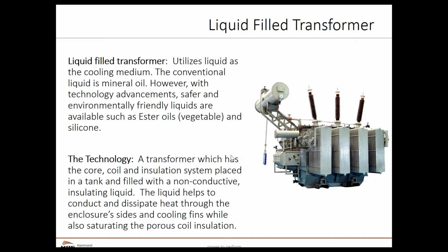In the case here, the picture we're showing is really what we term a high voltage transformer versus a medium voltage transformer. And high voltage transformers, as we will talk about soon, really are the domain of liquid filled. Medium voltage or dry type transformers really are only applicable to applications that are 44 kV and below. Anything higher than that, and you're really probably looking at liquid filled. There are some transformer manufacturers that will go up to 69 kV class, but for the most part, anything above 44 kV will be a liquid filled transformer.